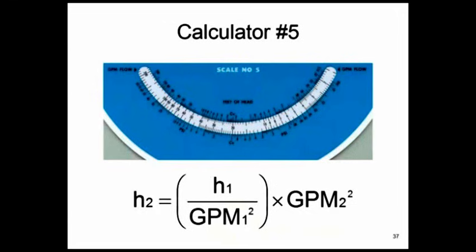And that's what scale 5 is on the system sizer. It's nothing but that square relationship to allow you to do balance. Every balancing thing in the world you play with is based on that fundamental scale 5 of the system sizer. Now on the plastic system sizer, the handheld is for specific gravity of 1, specific heat of 1. If you go get the Android version or the other version, you can correct it for other specific gravities. But for water, we use 1. For chilled water and hot water and so on, we're fine.